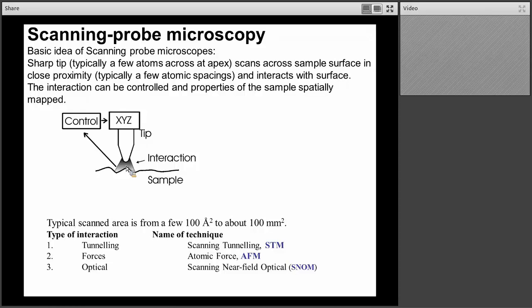The primary scanning probe microscope techniques I want to focus on are the scanning tunneling microscope, where the interaction is quantum tunneling between a probe a few angstroms from a conductive surface, and the atomic force microscope, which has many different interactions we can play with. The way the scanning probe microscope works is that we monitor that interaction — we have a sensor which detects the strength of the interaction and a control loop which monitors it and keeps it at some set value. The probe or tip is mounted on an actuator which scans across the surface, and the control loop controls the distance between the probe and the surface to control the interaction.